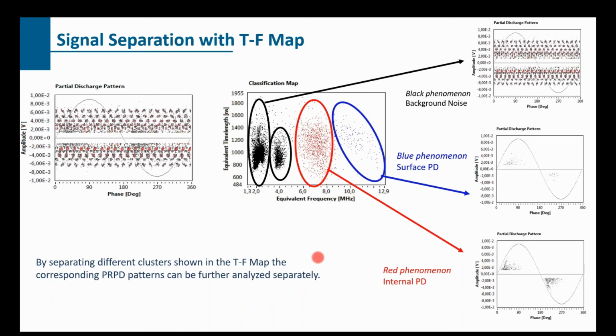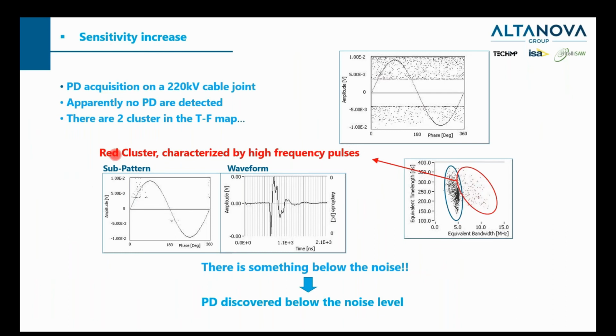So, a short summary: with the TF map, we can separate different clusters in the phase resolved pattern, and then we can do analysis for each individual class. There are two advantages here. First, we can recognize what type of signal is noise and what type of signals are PD signals. And second, even if we are dealing with multiple PD sources, with the TF map, we can recognize PD signals from different sources. And the third advantage is here.